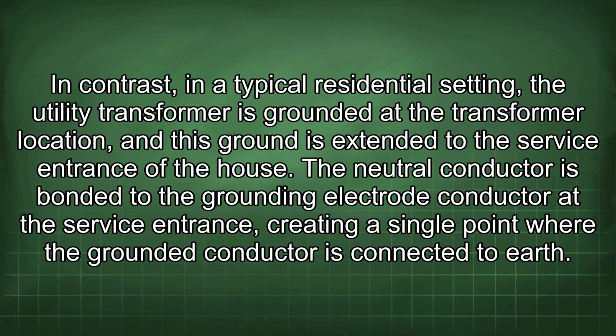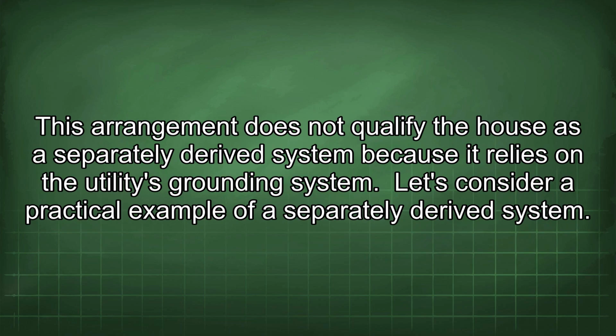In contrast, in a typical residential setting, the utility transformer is grounded at the transformer location, and this ground is extended to the service entrance of the house. The neutral conductor is bonded to the grounding electrode conductor at the service entrance, creating a single point where the grounded conductor is connected to earth. This arrangement does not qualify the house as a separately derived system because it relies on the utility's grounding system.